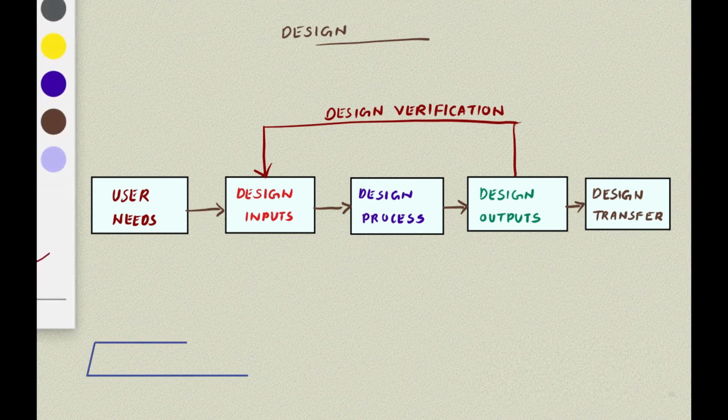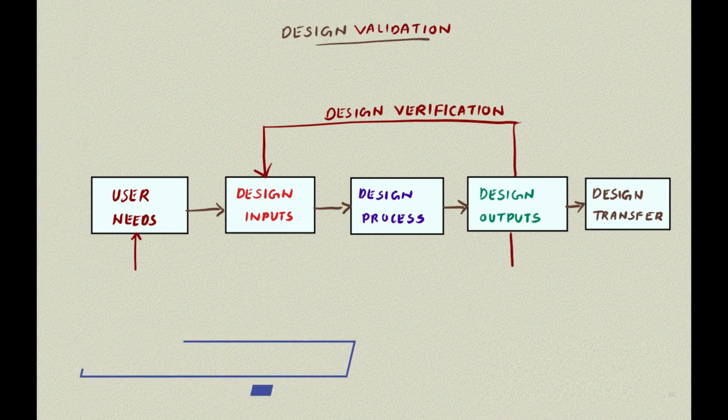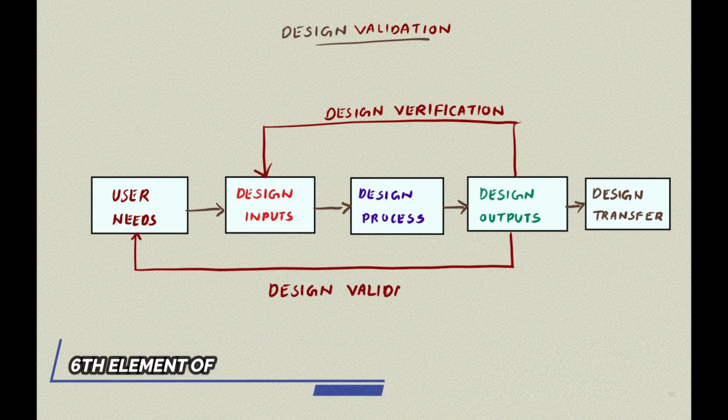Next is design validation. Here you validate the device design via examination, and objective evidence confirms that the final design output consistently meets the specified intended use. So basically, you're going to validate that the device you built works for the end user as intended.